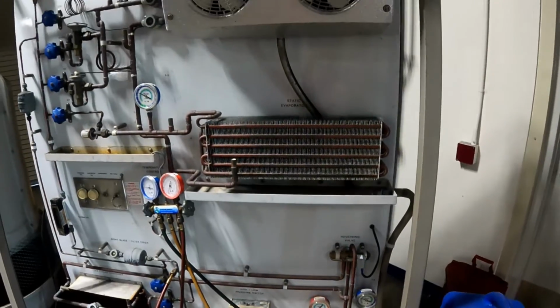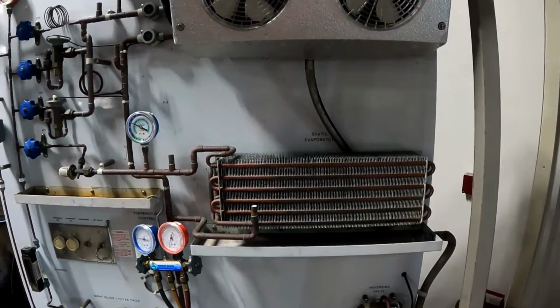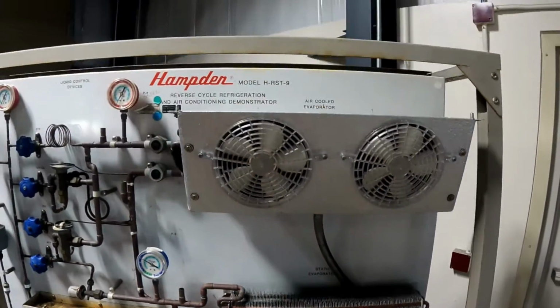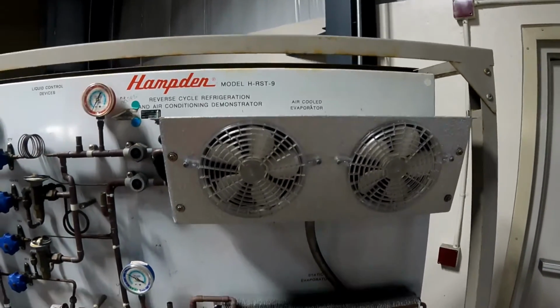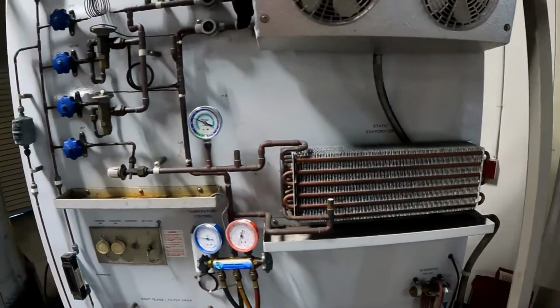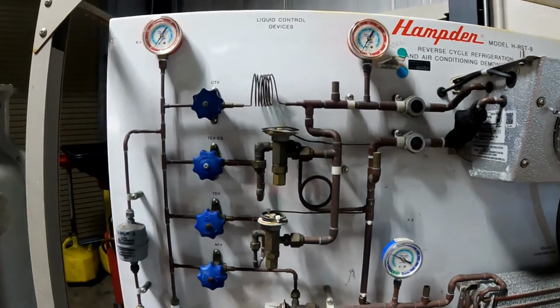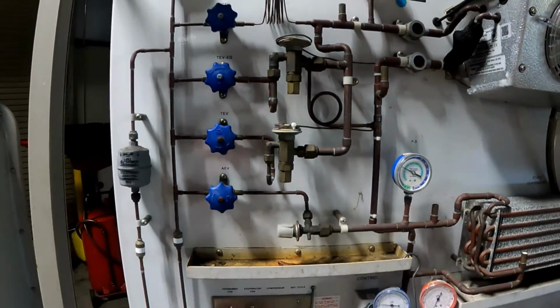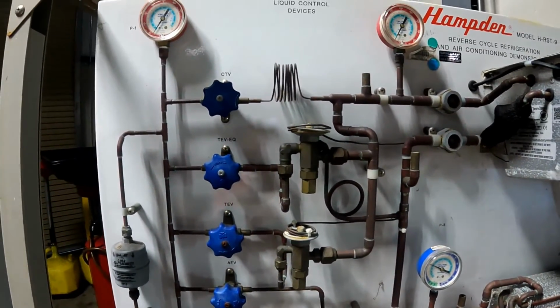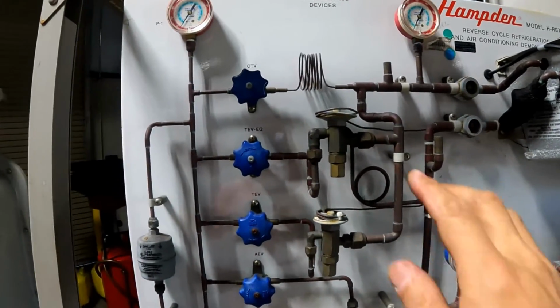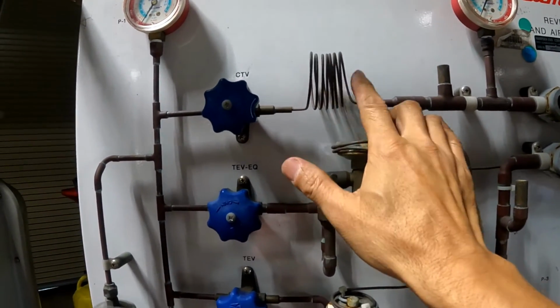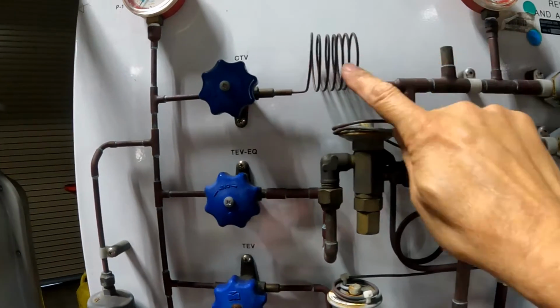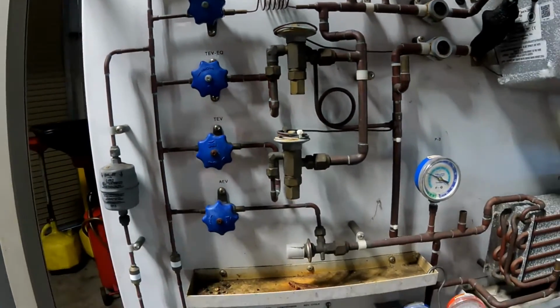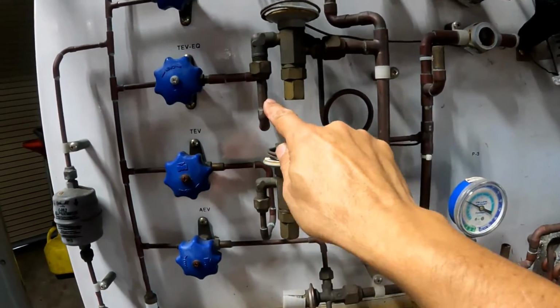And in this training equipment, we have two evaporators, one static evaporator and one air-cooled evaporator. Two evaporators. We have the different types of expansion valves commonly used. We have the typical capillary pipes, expansion valve, and we have the thermal expansion valve.